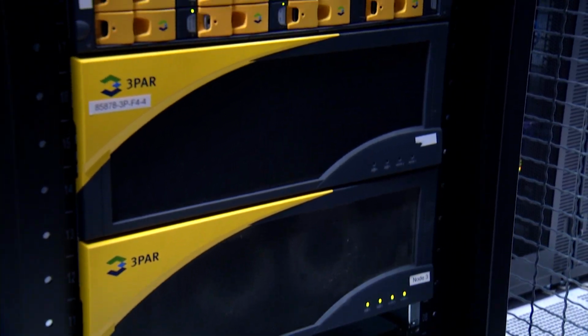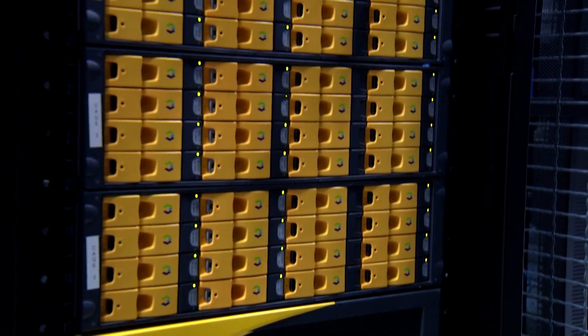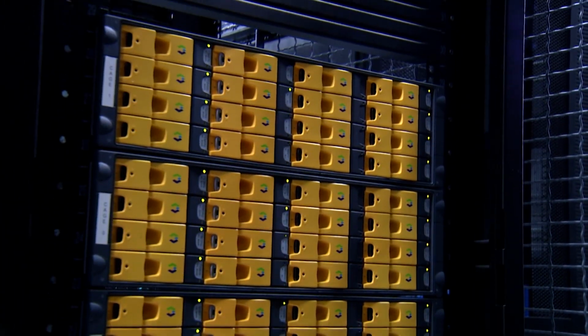So Jim, before we dig into the space-saving solutions, can you tell us a little bit about the constraints for three-phase distribution? First, most power engineers already use commercial three-phase power, but they split the three phases into single phase for consumption by the server blades in the rack. What kind of challenges? The data center operator is faced with the challenge of ensuring that each phase is evenly loaded. Uneven phase balancing creates a headache for the power generation utility, which is challenged with providing efficiently priced electricity for the data center. They see phase imbalance as an energy waste, and that has an impact on energy cost.